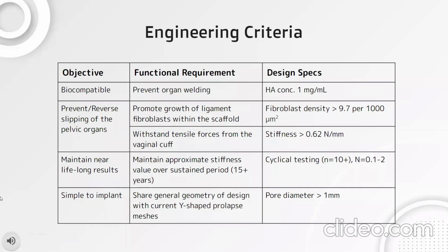We determined that the following engineering criteria would be appropriate. First, our device needs to be biocompatible to prevent the organ welding that current mesh devices can cause. To do so, our device should have a hyaluronic acid concentration of 1 milligram per 1 milliliter. Next, our device should prevent and reverse any slipping of pelvic organs. Therefore, we need this device to promote the growth of ligament fibroblasts within the scaffolding by having a fibroblast density of greater than 9.7 per 1,000 micrometers.